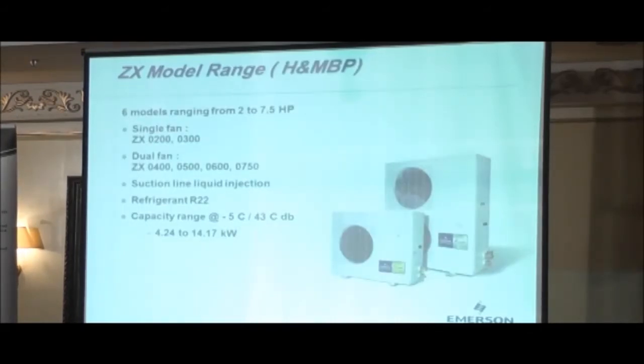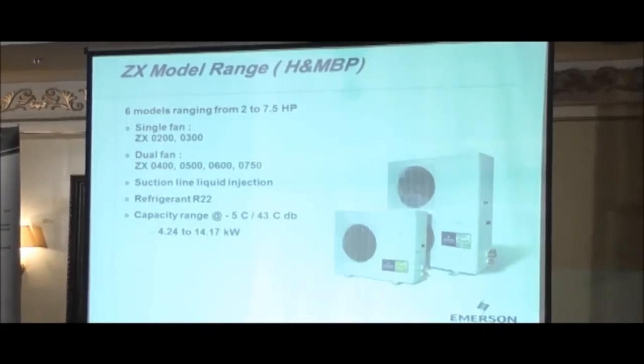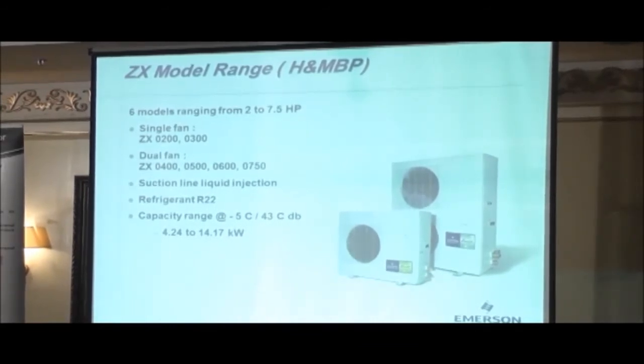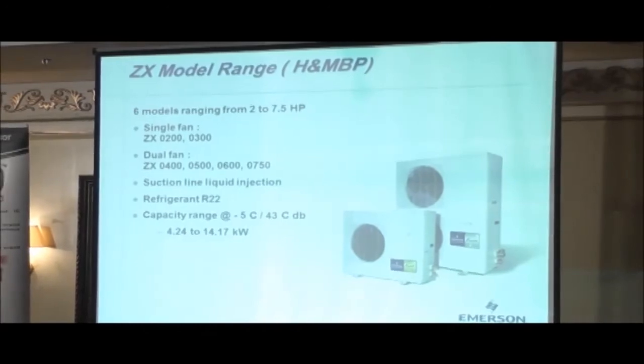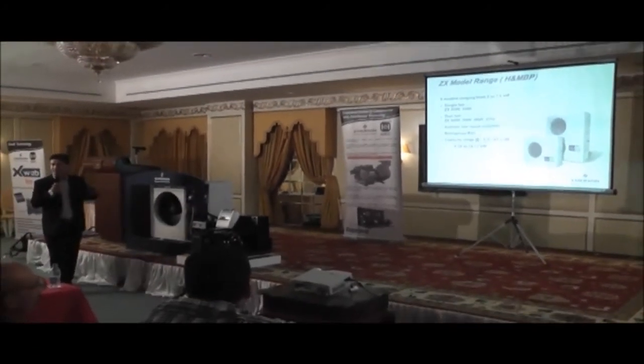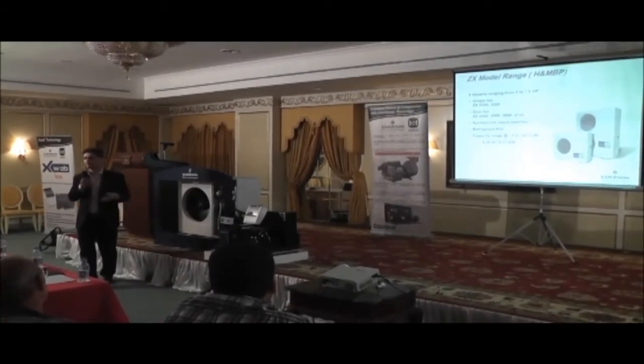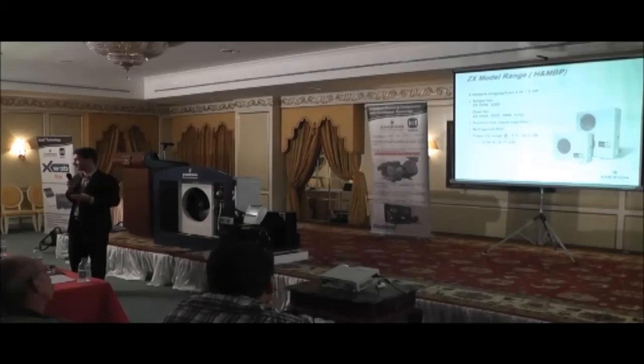But before we get to that, in terms of the range, we've got the ZX, which is a high back or medium back chiller unit. We've got 6 models from 2 to 7.5 horsepower. Single fan is the 2 and 3, and then 4, 5, 6, and 7.5 is the twin fan or dual fan. All the medium temp units use what we call suction line liquid injection. We inject liquid into the suction line to cool down the compressor. And those of you who have worked with semi-hermetics, it's very similar to demand cooling. If you understand demand cooling and how it works, we've adopted that concept and we're basically using demand cooling in this compressor as well. That's what we mean by suction line liquid injection.